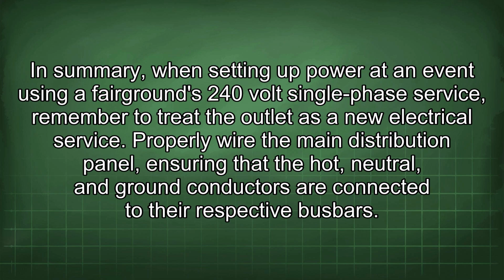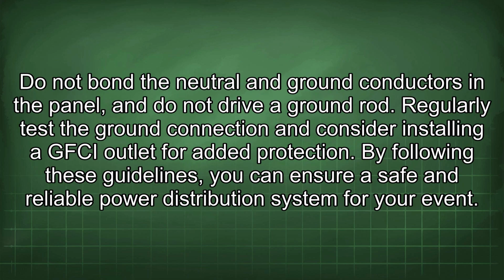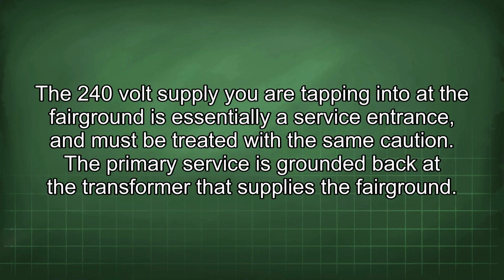Properly wire the main distribution panel, ensuring that the hot, neutral, and ground conductors are connected to their respective bus bars. Do not bond the neutral and ground conductors in the panel, and do not drive a ground rod. Regularly test the ground connection and consider installing a GFCI outlet for added protection. By following these guidelines, you can ensure a safe and reliable power distribution system for your event.